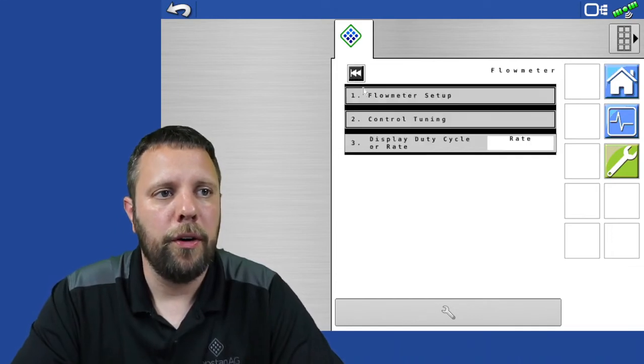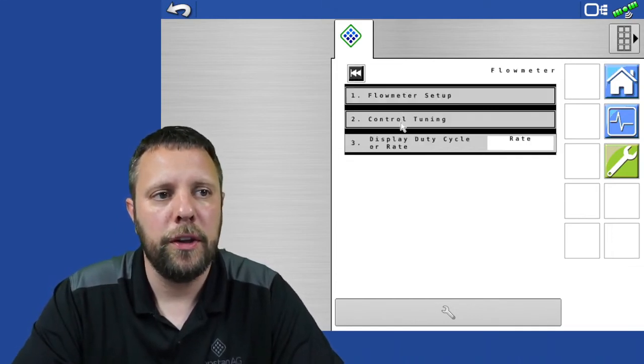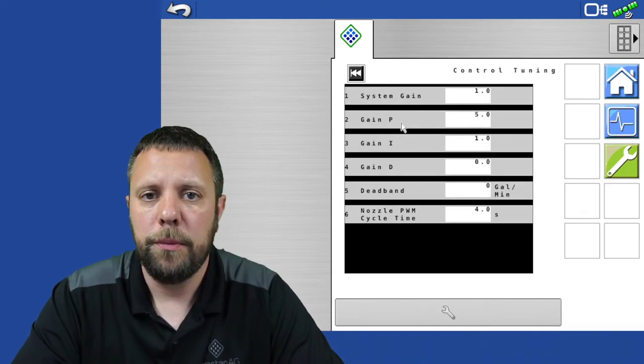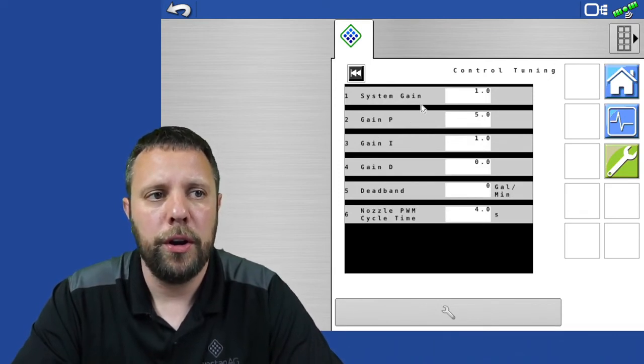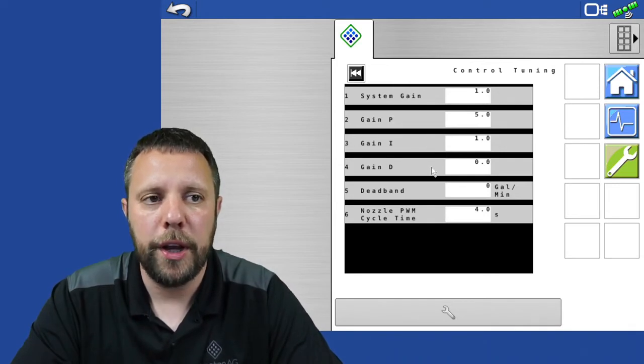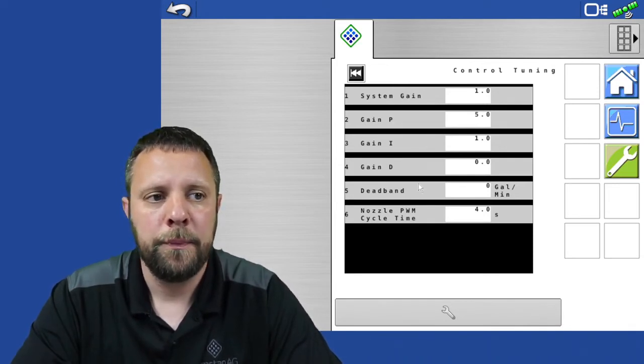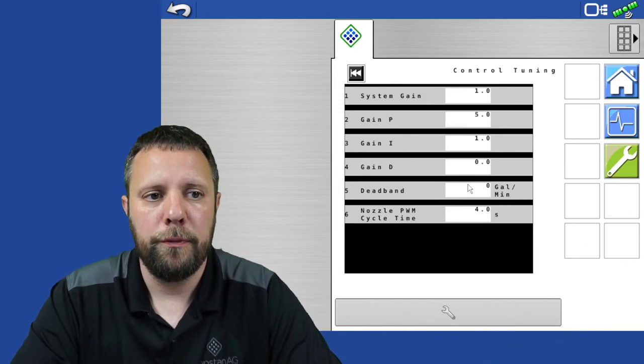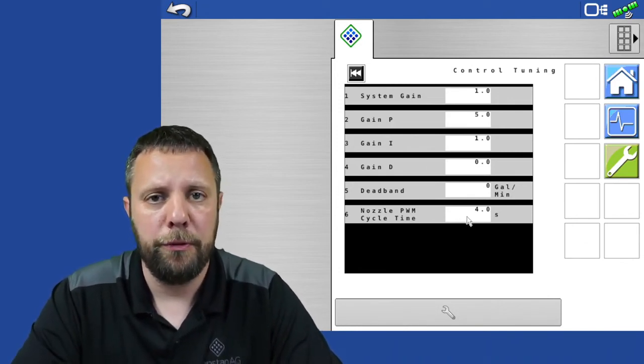So now that we've got our flow meter values and settings in, we'll go into the control tuning. Typically, the default values are good here. So system gain of 1, proportional integral differential gain set to 5, 1, and 0. 0 gallons per minute for the deadband, and a nozzle PWM cycle time of 4.